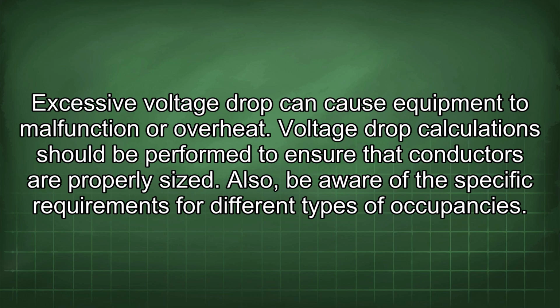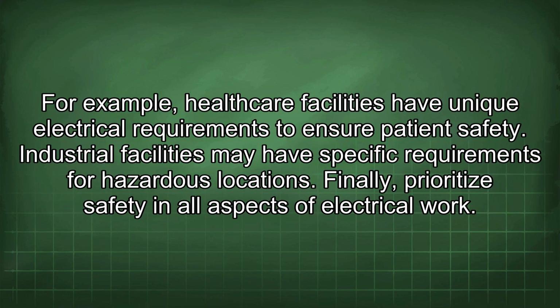Excessive voltage drop can cause equipment to malfunction or overheat. Voltage drop calculations should be performed to ensure that conductors are properly sized. Also, be aware of the specific requirements for different types of occupancies. For example, healthcare facilities have unique electrical requirements to ensure patient safety. Industrial facilities may have specific requirements for hazardous locations.